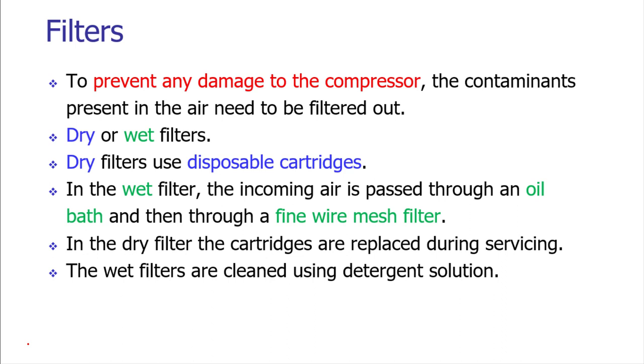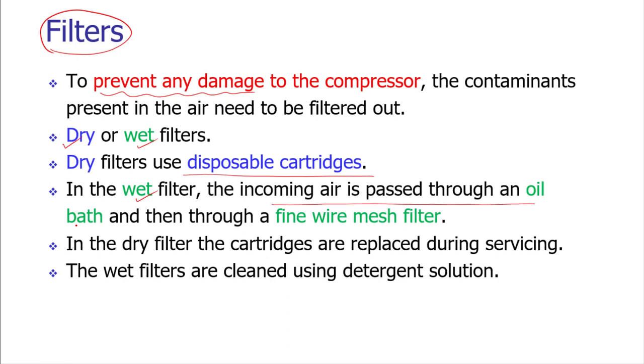The first element is filters. Filters are used to prevent damage to the compressor. We have dry and wet filters. Dry filters use disposable cartridges containing a chemical that removes water vapors from the compressed air. In wet filters, the incoming air is passed through an oil bath and then through a fine wire mesh to dry the air. After use, dry filter cartridges must be replaced, while wet filters are cleaned regularly using a detergent solution so they can be reused multiple times.